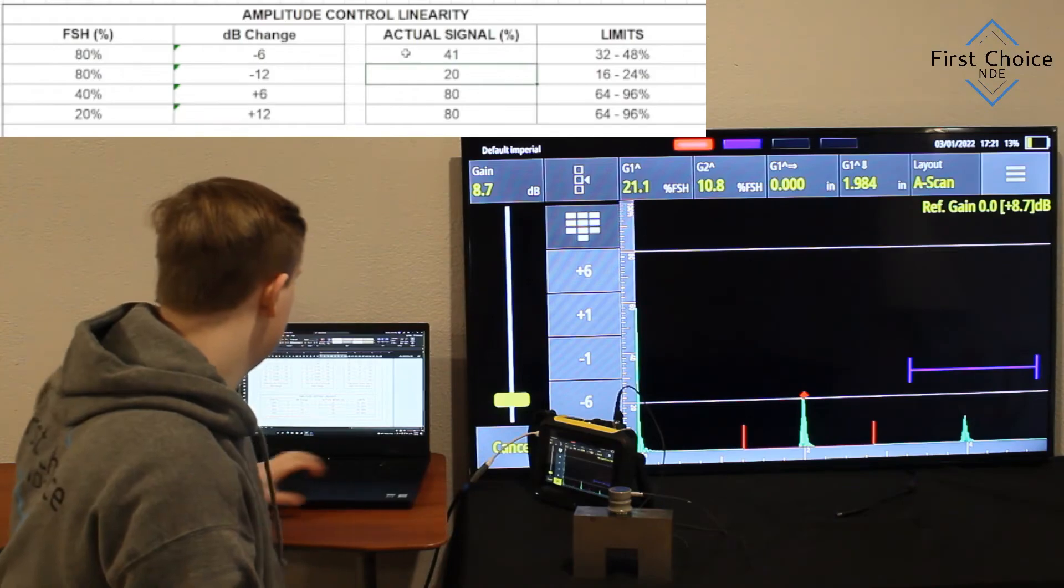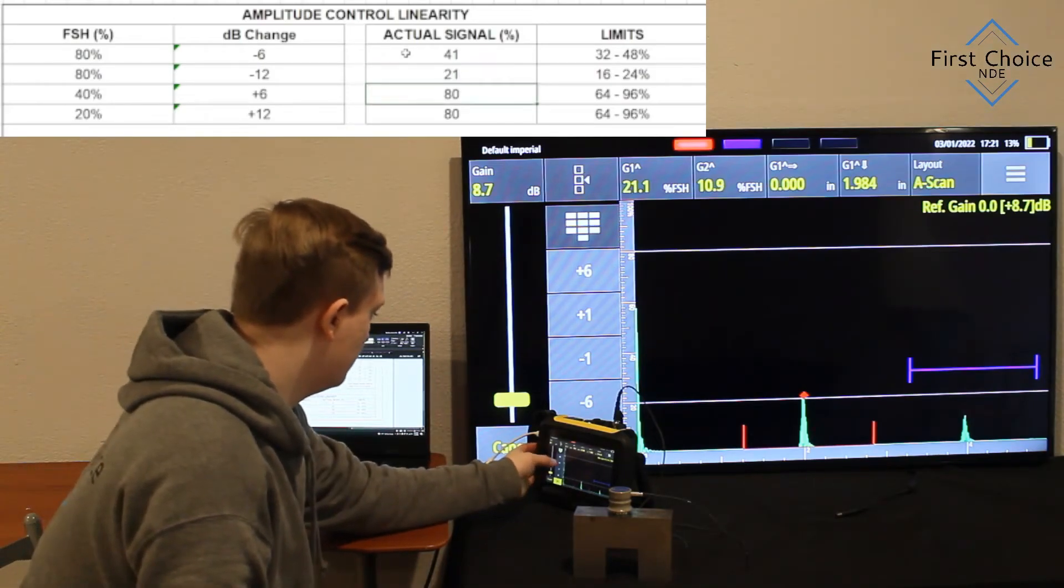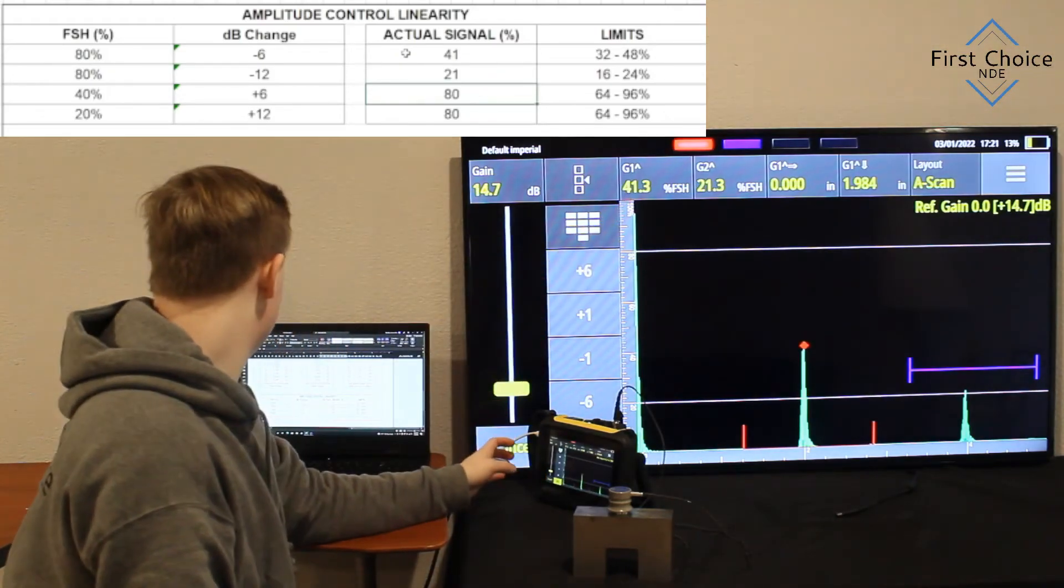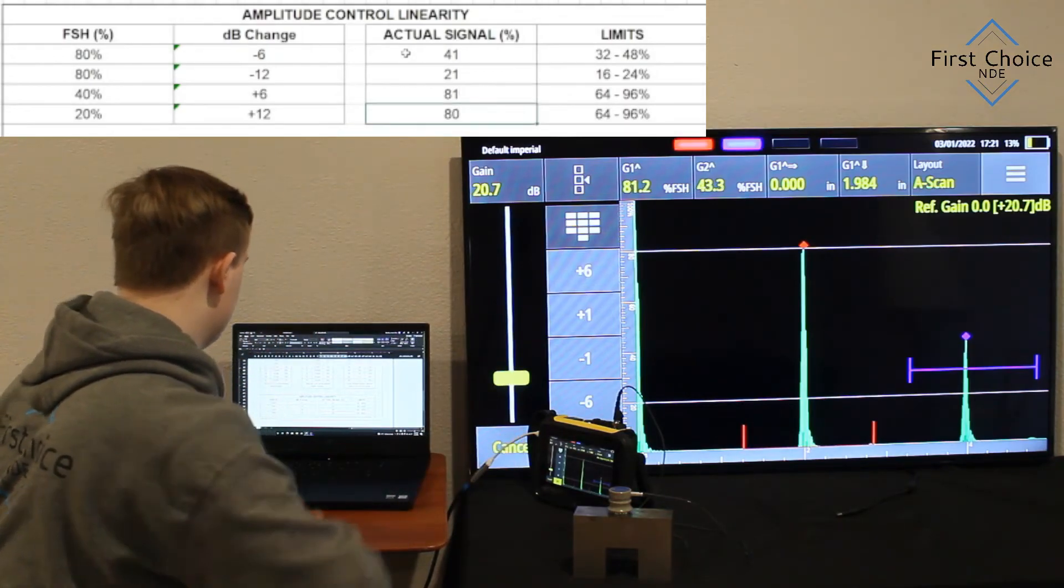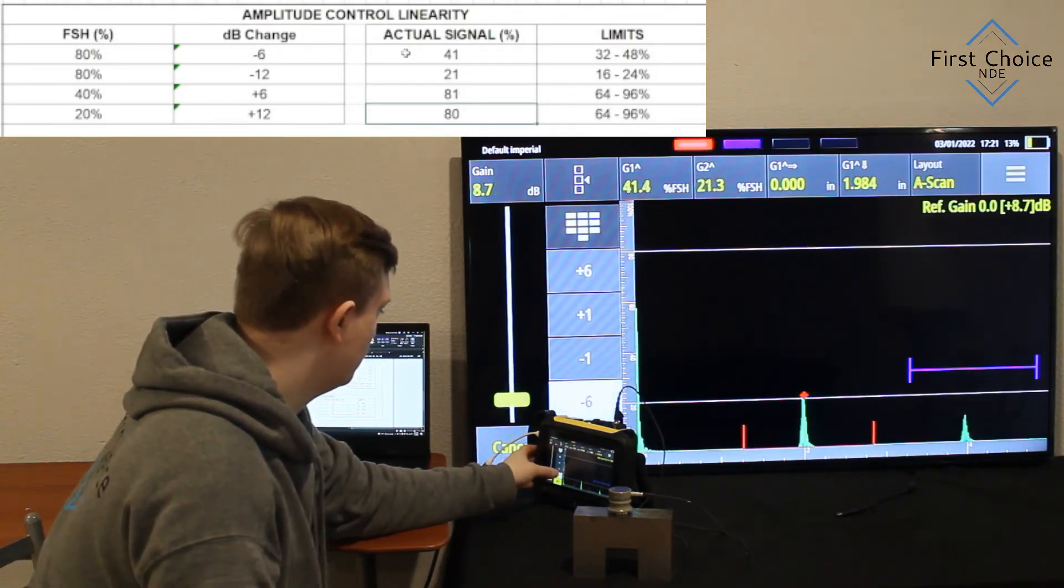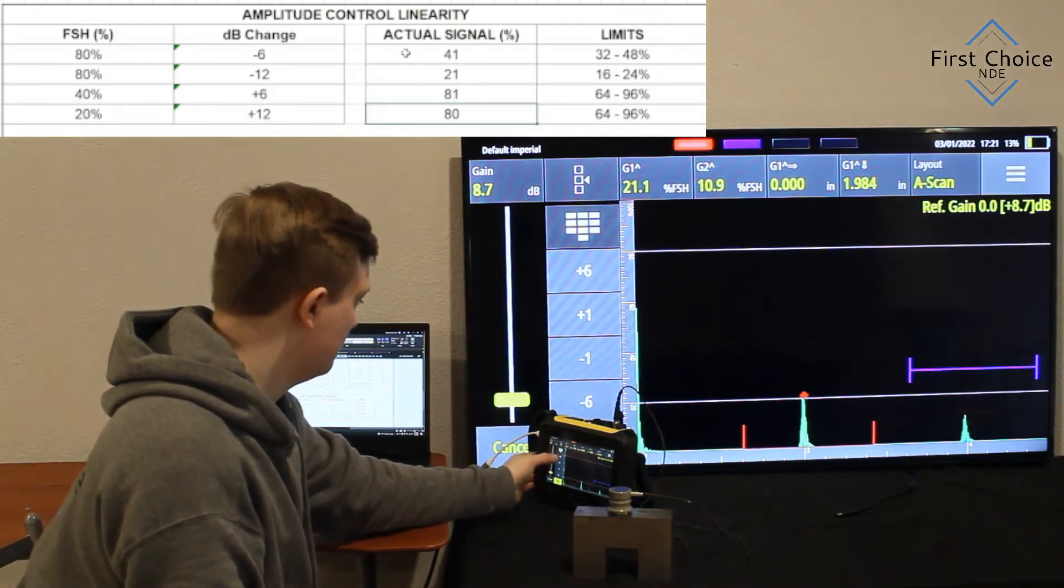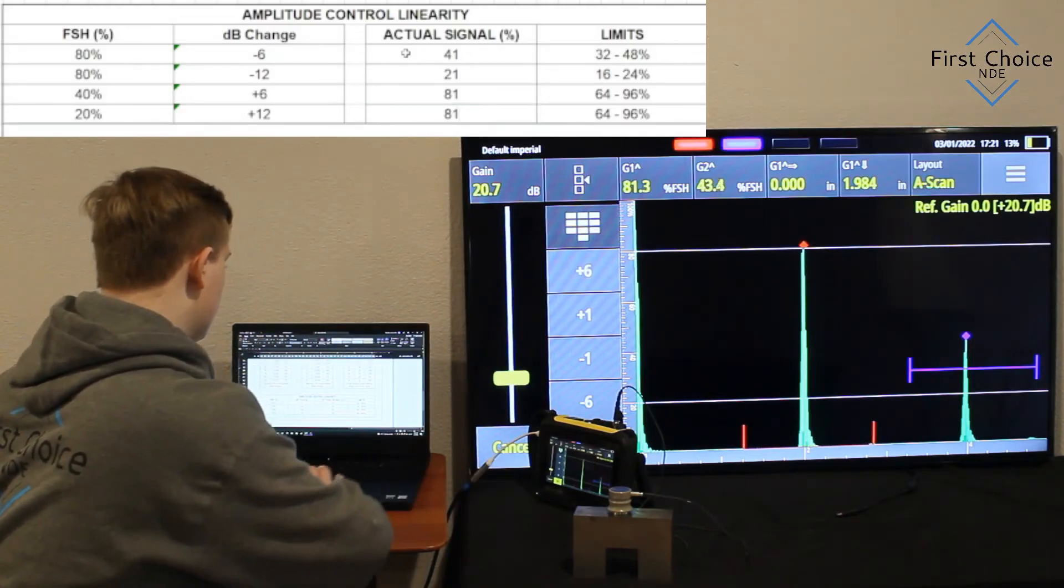Alright, so we go back to 80, and we drop it 12 dB, which will go 40 to 20. And ours is 21, so 1 dB off. So now we go start at 40% screen height, raise it 6 dB, and that should bring us to 80. We're at 81. Alright, now you start at 20%, and you're going to add 12 dB, which should bring you to 80%, and ours is 81.